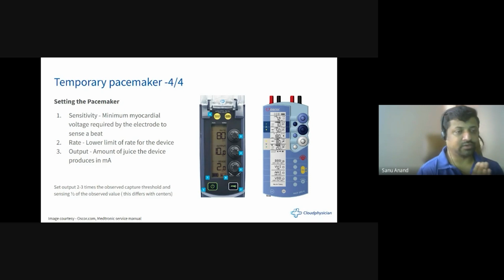So if the heart rate falls, in this case one is set at 80, the other one is set at 72. So if the heart rate falls below 80, then the pacemaker will kick in. And output is the amount of electricity which goes into the heart from the pacemaker. It's the amount of juice the device produces in milliamperes. How do we set it?